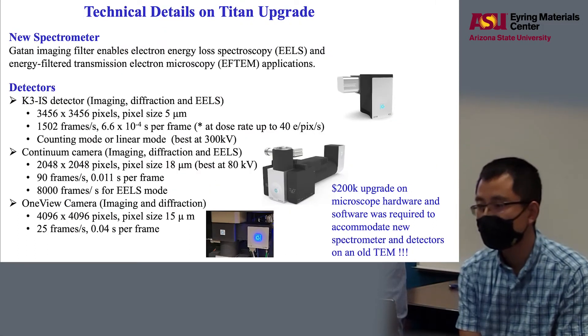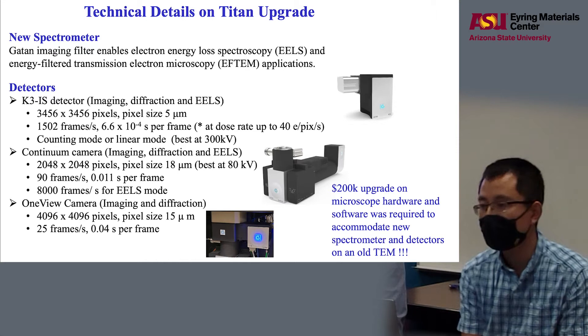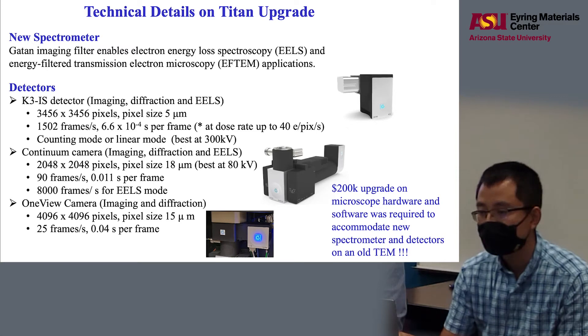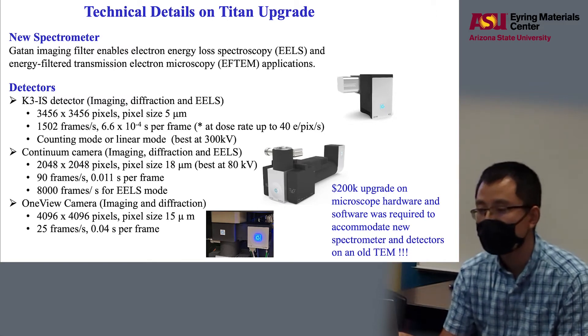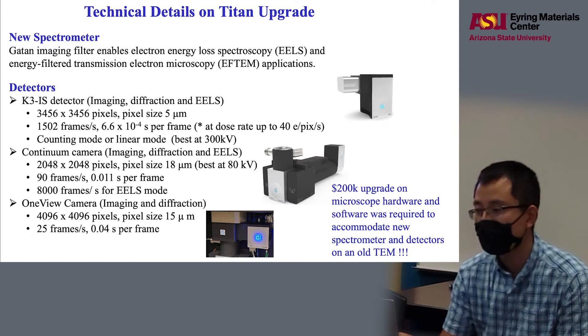Here are some technical details on the Titan upgrade. We have a new spectrometer — the Gatan imaging filter enables both EELS and also energy filter imaging. We have three new detectors. The major one is the Gatan K3-IS detector, which offers imaging, diffraction, and EELS with a large pixel array and a pixel size of 5 micrometers. It can read out very fast at 1,500 frames per second, but only at a low dose rate — at most 40 electrons per pixel per second.